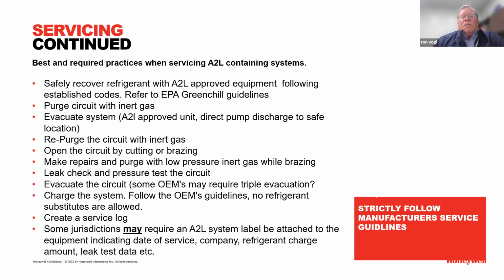This is just a little more on servicing. Use inert gas, as I already mentioned. There may be rules in place that you have to vent your vacuum pump to a safe location away from where you're working. Again, leak checking, create a service log, and all I can really say is follow the OEM's guidelines. They're going through all of this with UL and the rest of it. So do it right, do it safe. And if they call for, for example, triple evacuation before you do something, just follow the rules. Everyone's going to have to do the same thing.